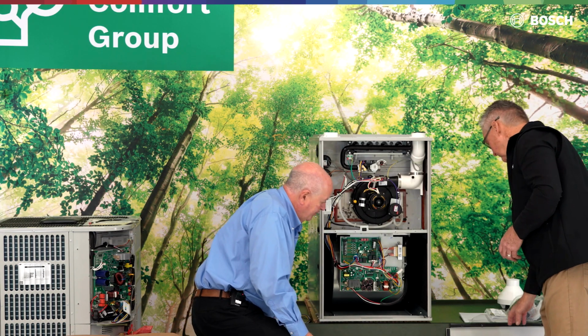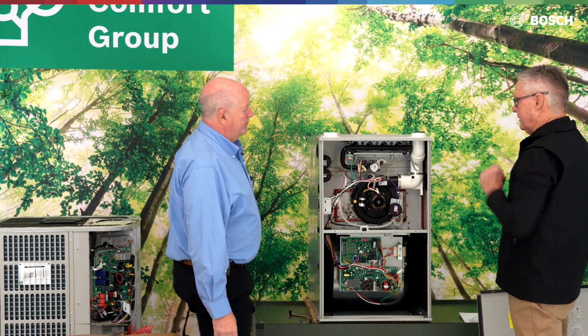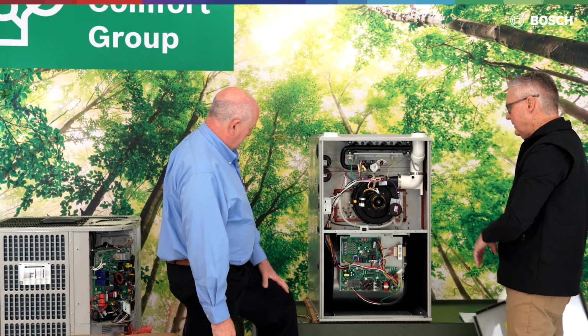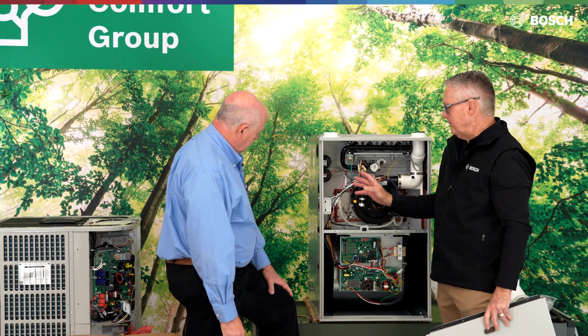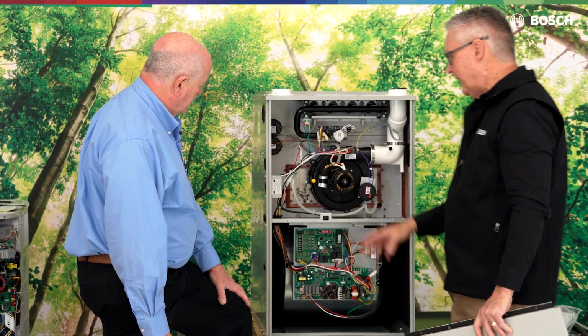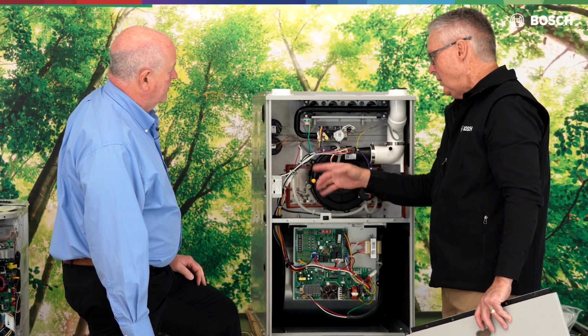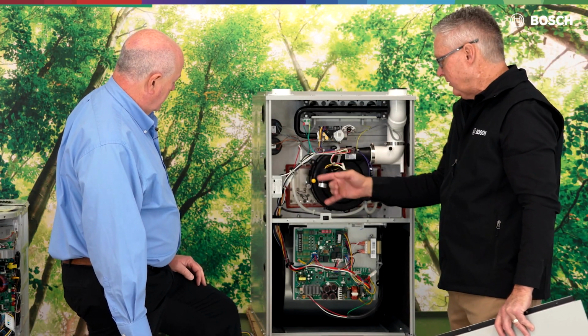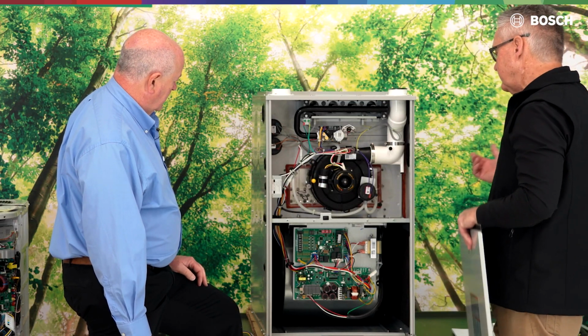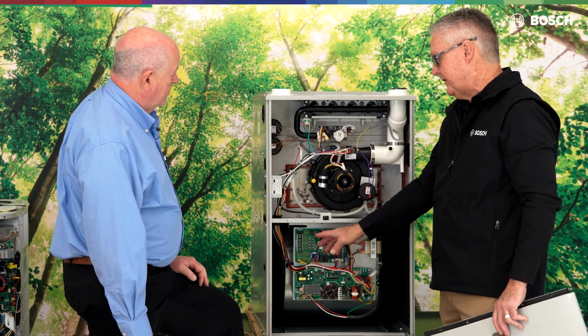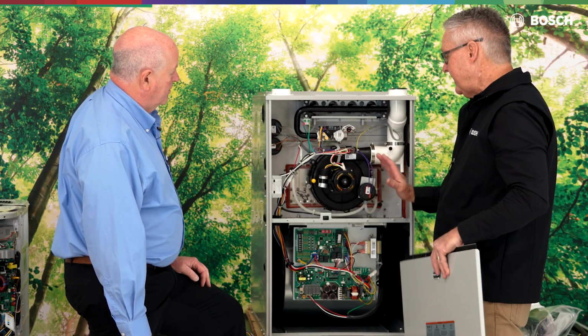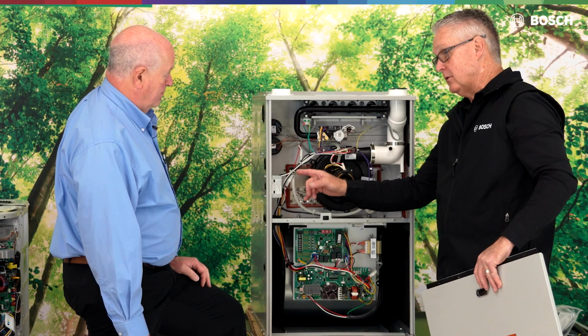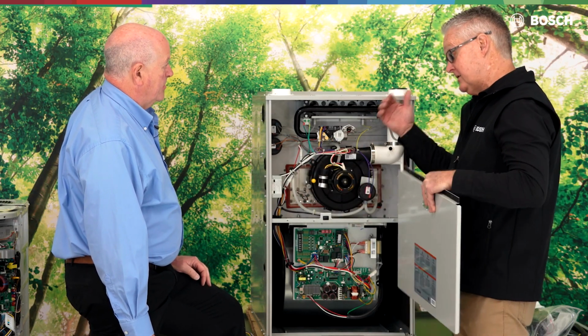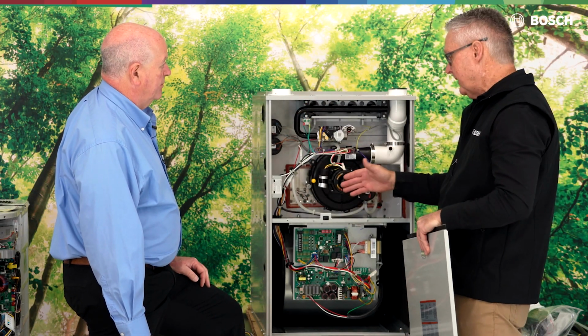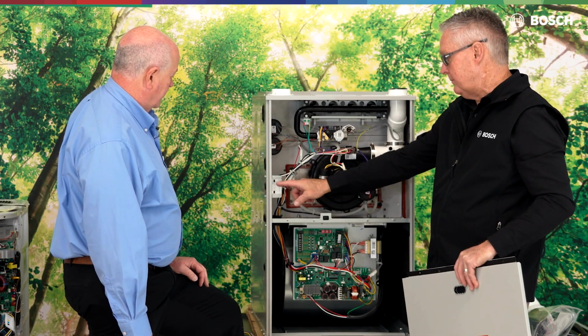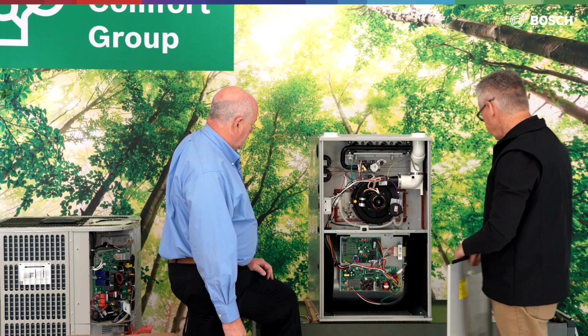First. So in the process of installing this in the summertime, I'm in a hurry, it's hot, I hook up the electrical, I don't care about the L1 and the neutral, and I reverse those. When the polarity is reversed, and this wants to be a heater in the wintertime, it is going to give me a code that basically says, hey, I can't work with that polarity reversed. I'm not going to light, but I'll run as a fan for the air conditioner. I'm not going to light as a heater, and that's why we have to come back and reverse that polarity at that point in time.